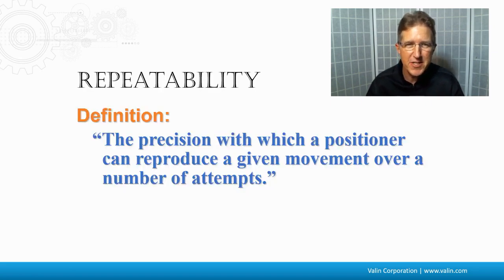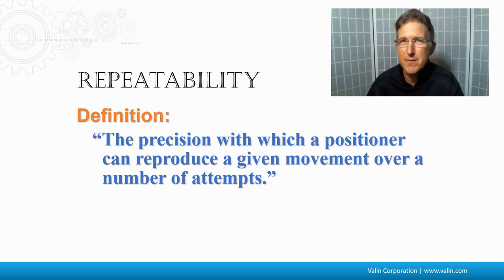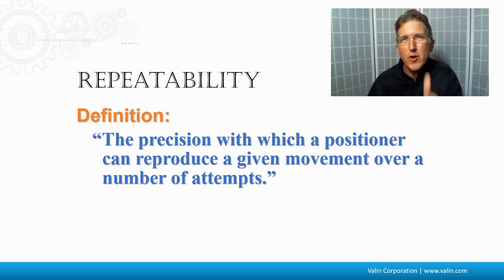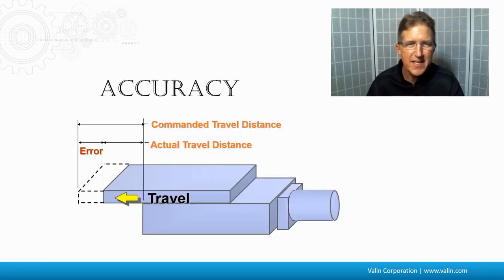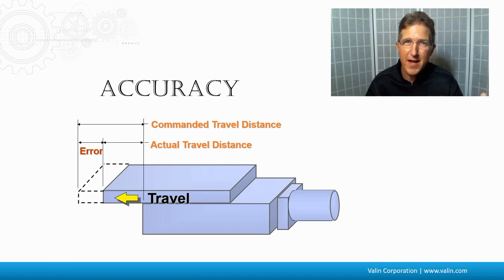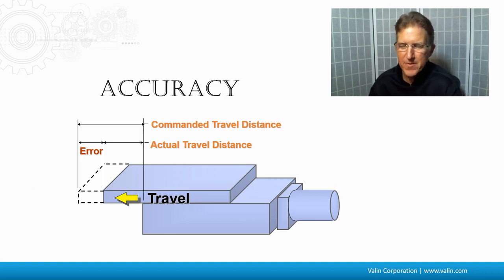Repeatability — the definition — is the precision with which a positioner can reproduce a given movement over a number of attempts. In other words, it's how repeatably you can go to the same location. Accuracy is the difference between where you command the actuator to go versus the actual location it goes to, and there's going to be some error between them.